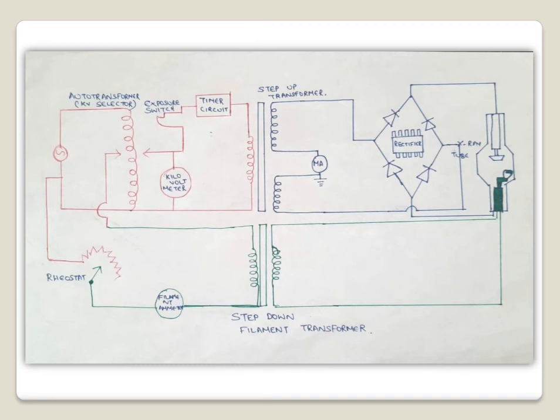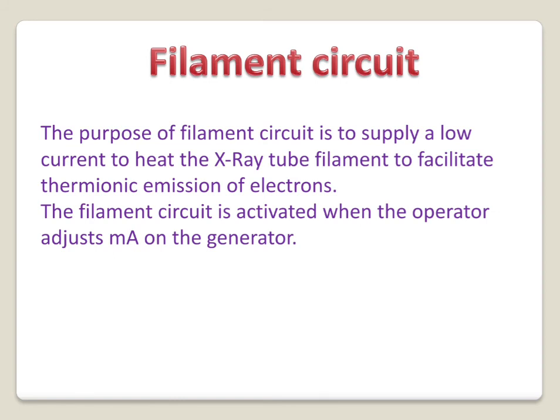So these are all the different circuits present in the x-ray circuit. The filament circuit is activated only when the operator adjusts the milliampere on the generator, and its purpose is to supply current to heat the x-ray tube filament. The purpose of the secondary circuit is to provide direct current to the x-ray tube. The primary circuit acts as a source of power for both the secondary and the filament circuit.